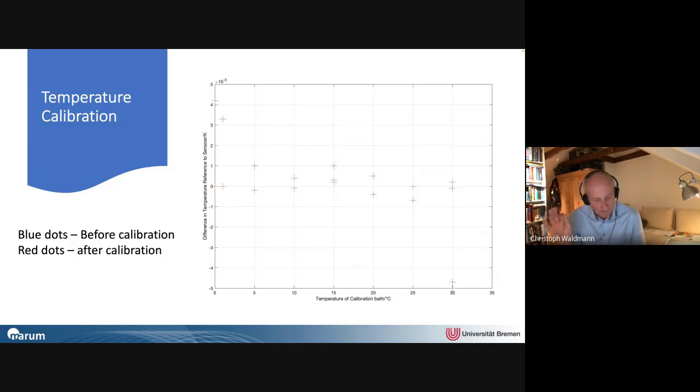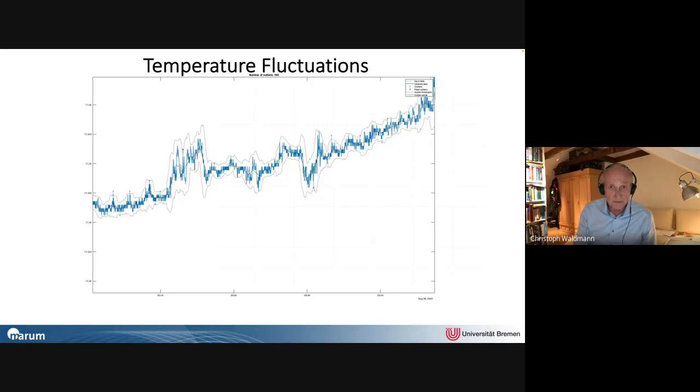So the absolute uncertainty, or the absolute temperature value, you have to expect an uncertainty of the order of 3 or 4 millikelvin. So I know this is something that needs some more explanation, discussion, but if you like, we can enter this later on.